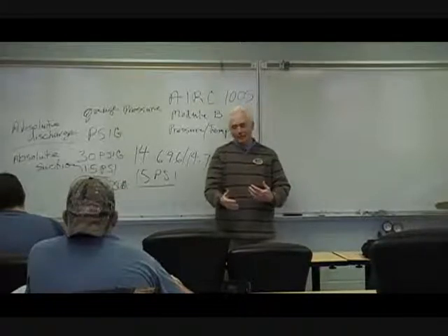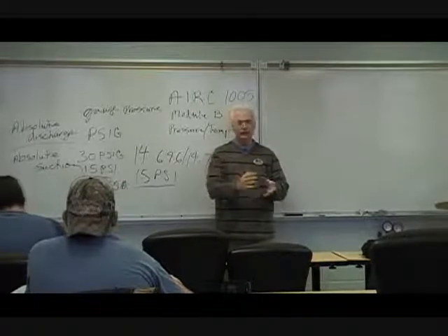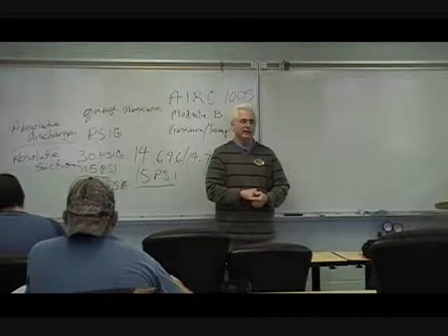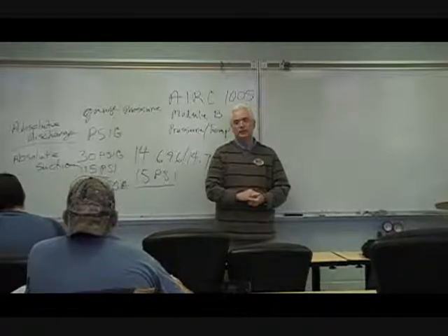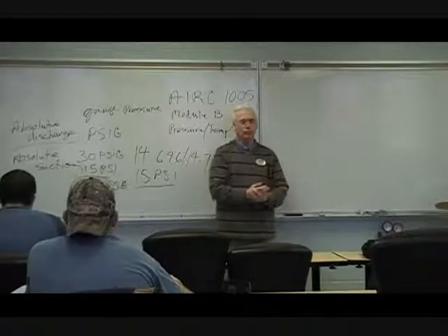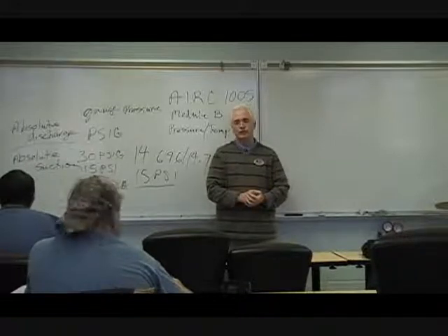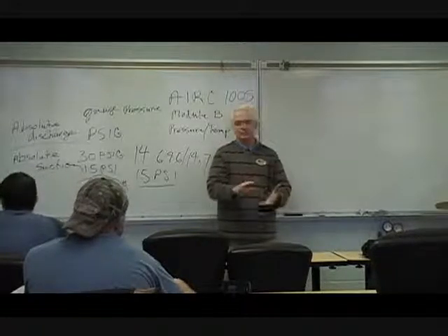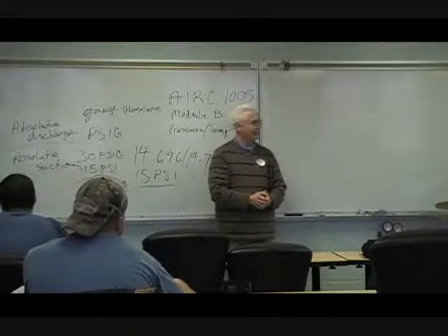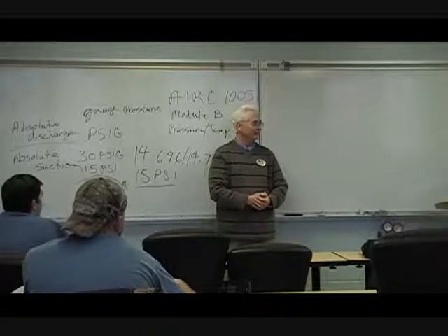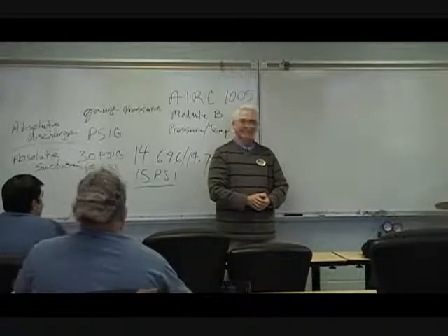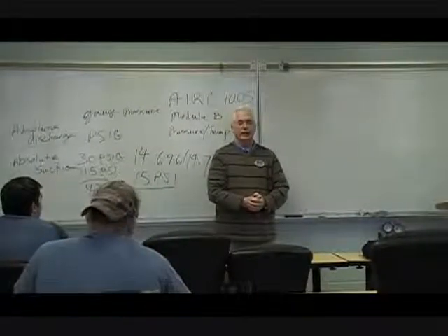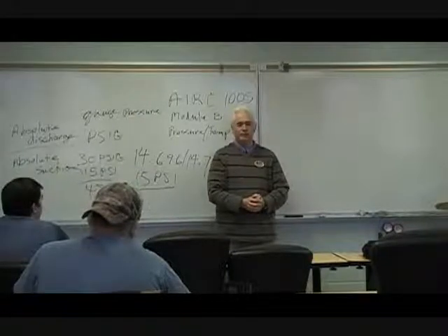Now when we get into some of the refrigerant blends, that's going to change a little bit because you have what's called temperature glide, and that's another lesson in itself. But most of the time you can measure the pressure on that system, look at your PT chart, and determine what temperature that refrigerant is inside the system based on that pressure. Is that making sense to anybody? Pressure-temperature relationship? I hope it is. We'll conclude this part of the video lecture, and we'll continue our lessons on pressure-temperature relationships.